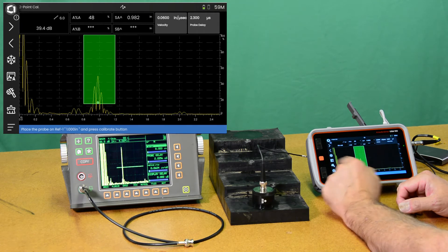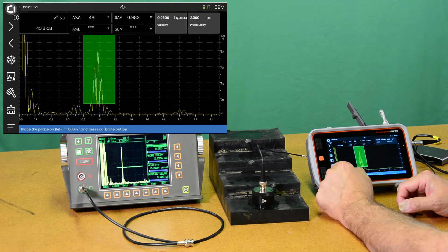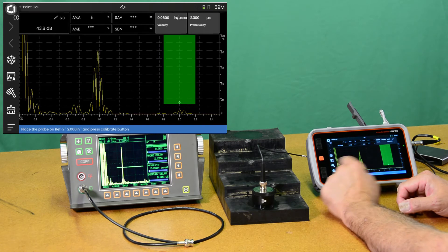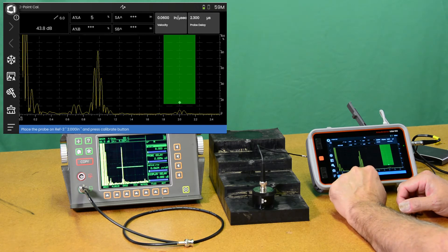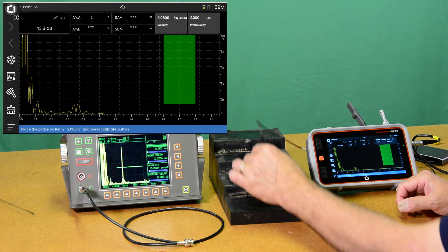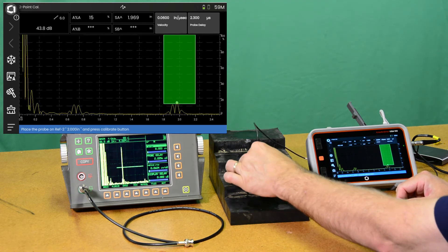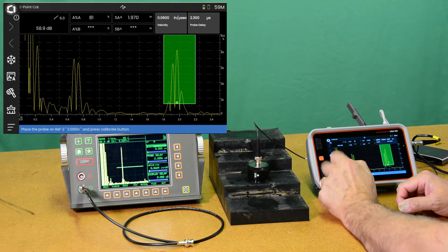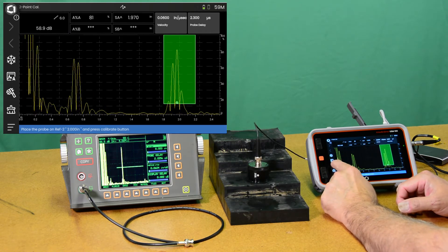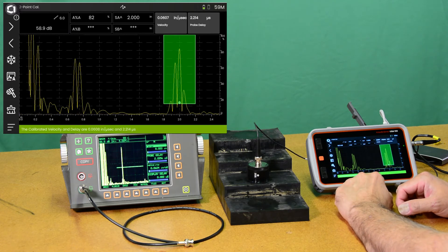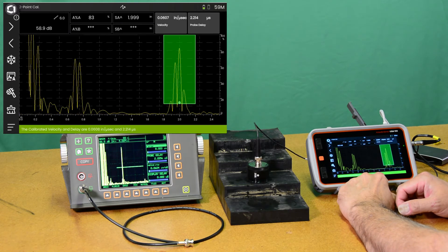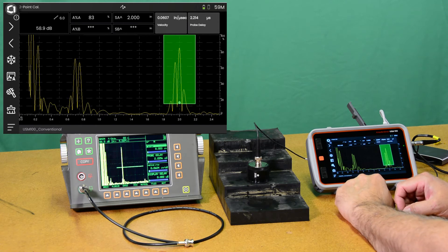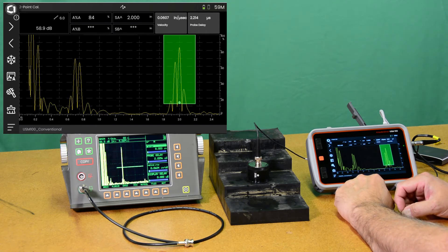And we're going to do a multi-step calibration. My gate is already over my one inch echo. I can do auto 80 and hit calibration. Now it's telling me to go to the second step, reference two, with two inch. So I can do that. Do auto 80. Calibrate. And it comes up with 0.0608 inches per microsecond and 2.214 microseconds of delay.